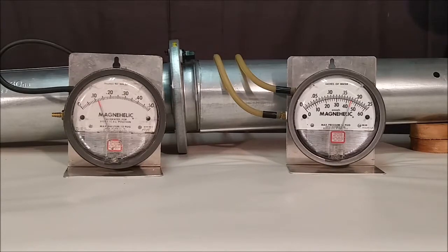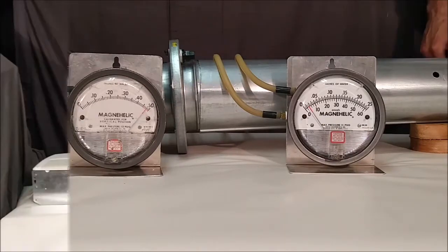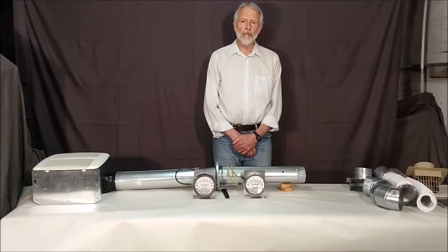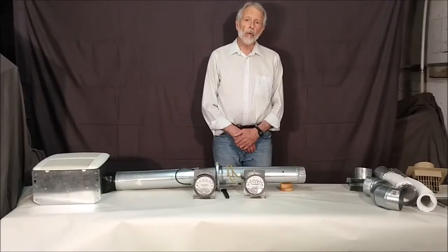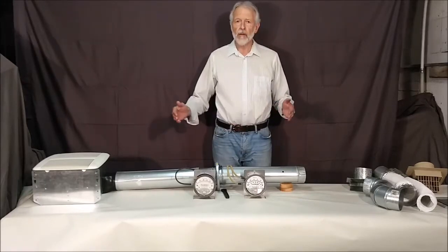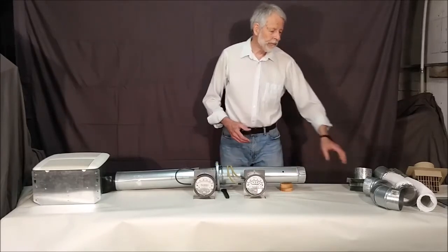The extreme opposite condition is if the duct is completely closed off, the fan wheel accelerates to higher RPM, the pressure comes up to shut-off condition, and the flow rate goes to zero. Each of the fittings that we will attach to this ductwork will show that the fan performance is reduced.